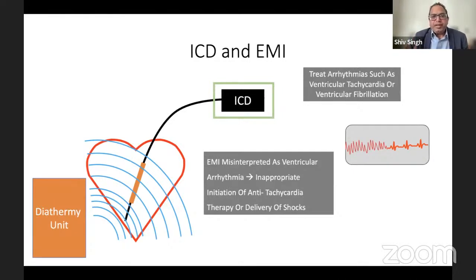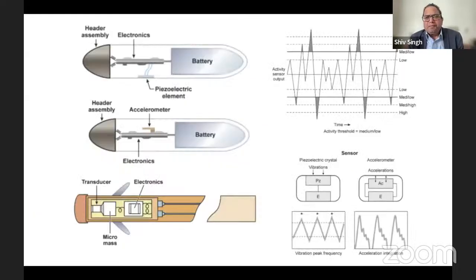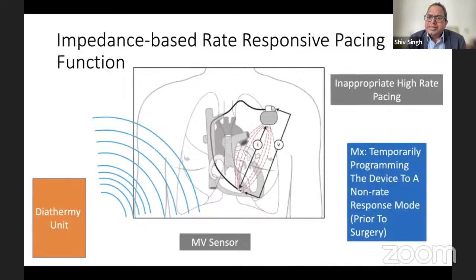Then there are various sensing parts within the pacemaker leads, known as the impedance-based rate responsive pacing function. What these do is sense when you're breathing, your chest expands, isn't it? So it will sense the distance between the tip and the pacemaker unit. The more rapidly you breathe, that means you're using more oxygen, so it will increase the rate. Like in exercising, your minute ventilation will increase. They will sense this increase in minute ventilation and accordingly change the response of the pacemaker. So these can be damaged. If these are damaged by diathermy, then the whole unit has to be changed.